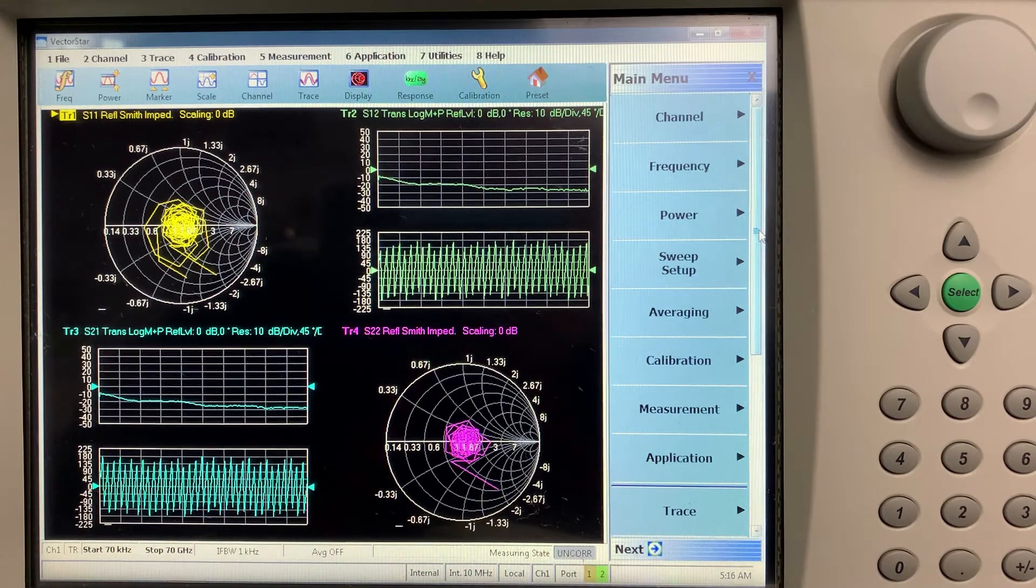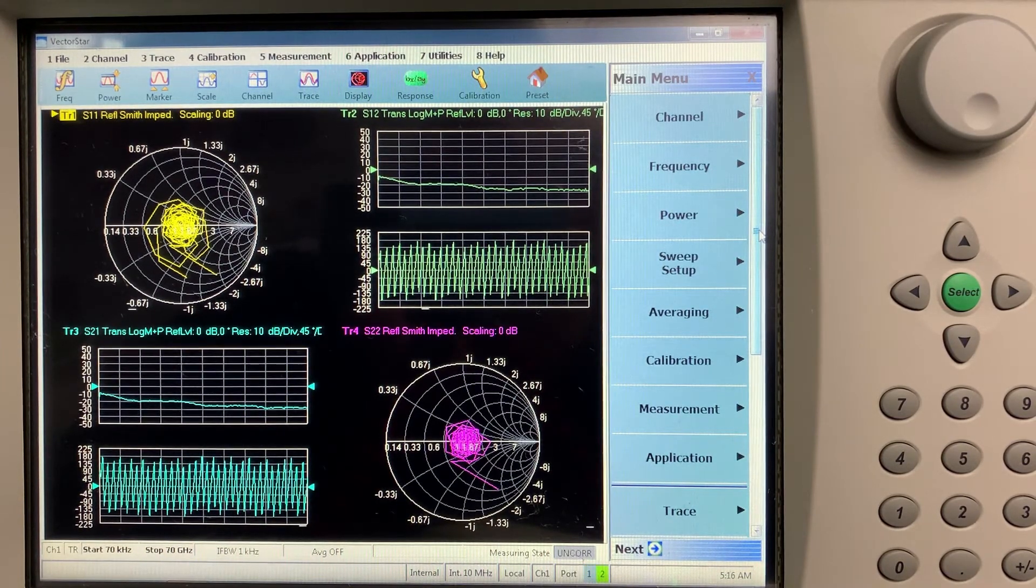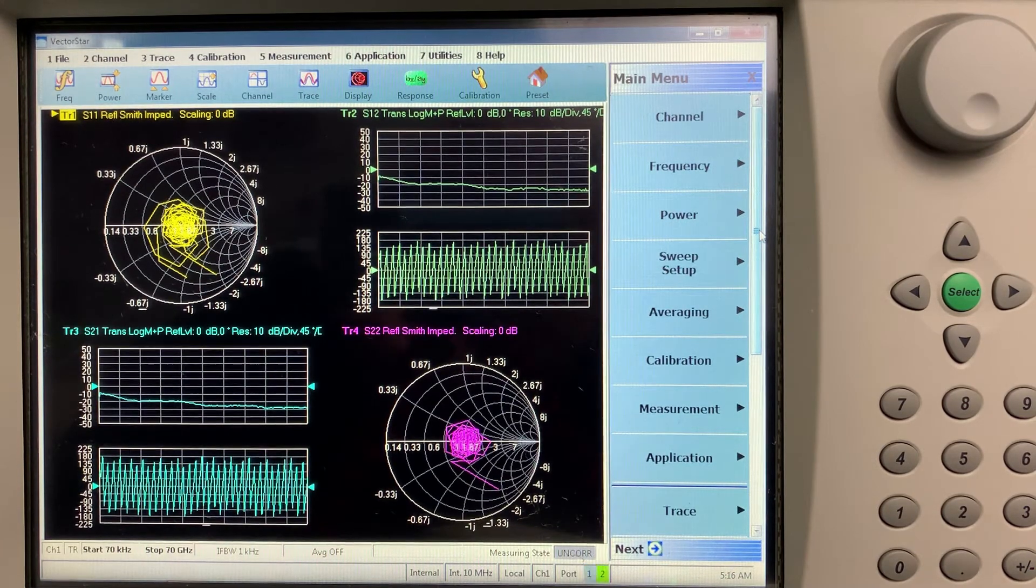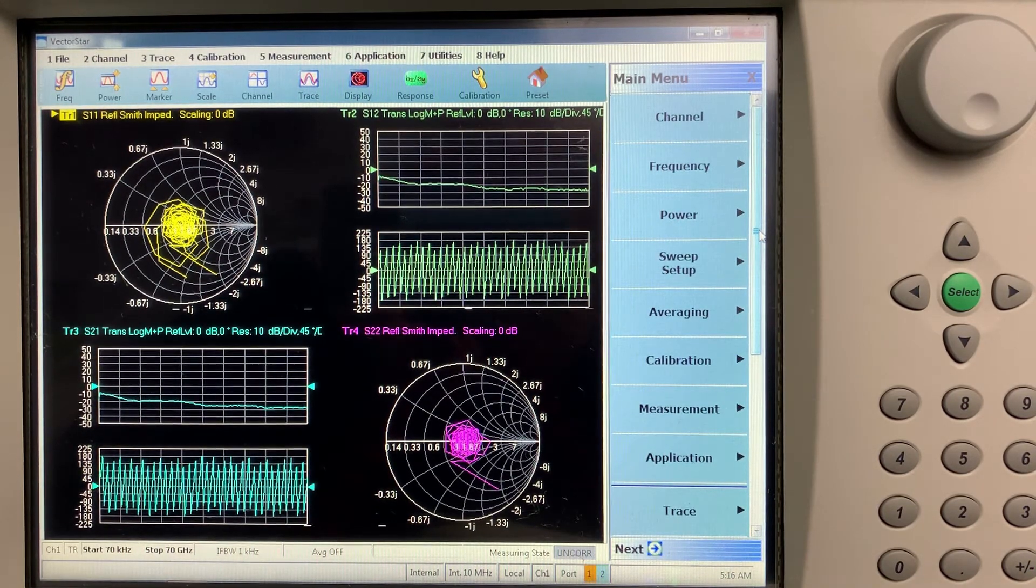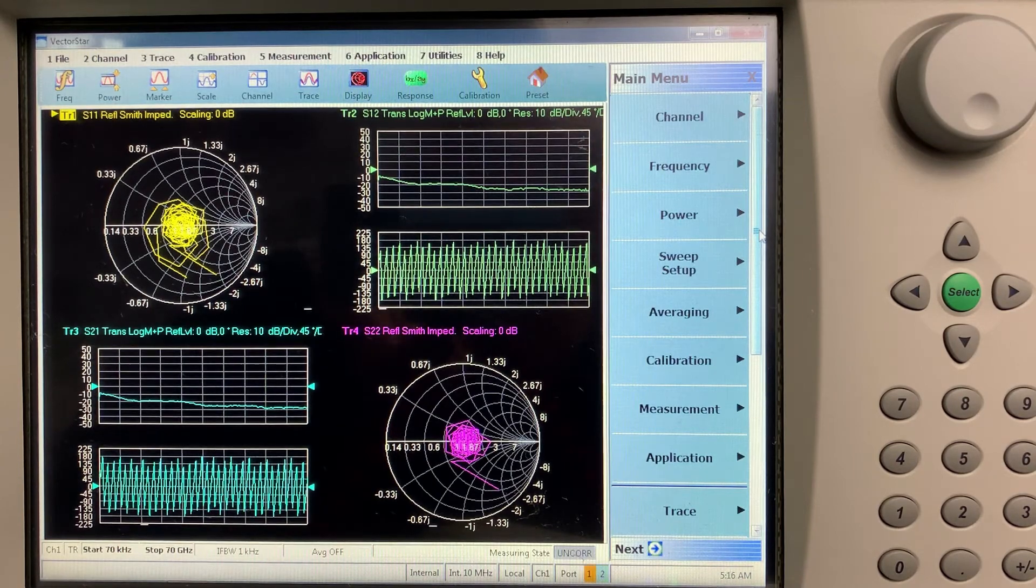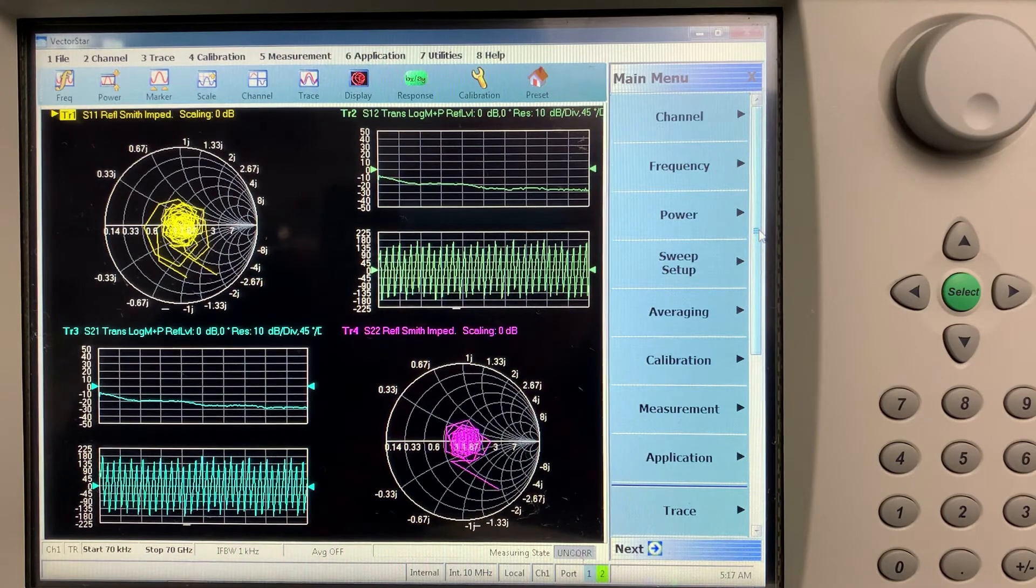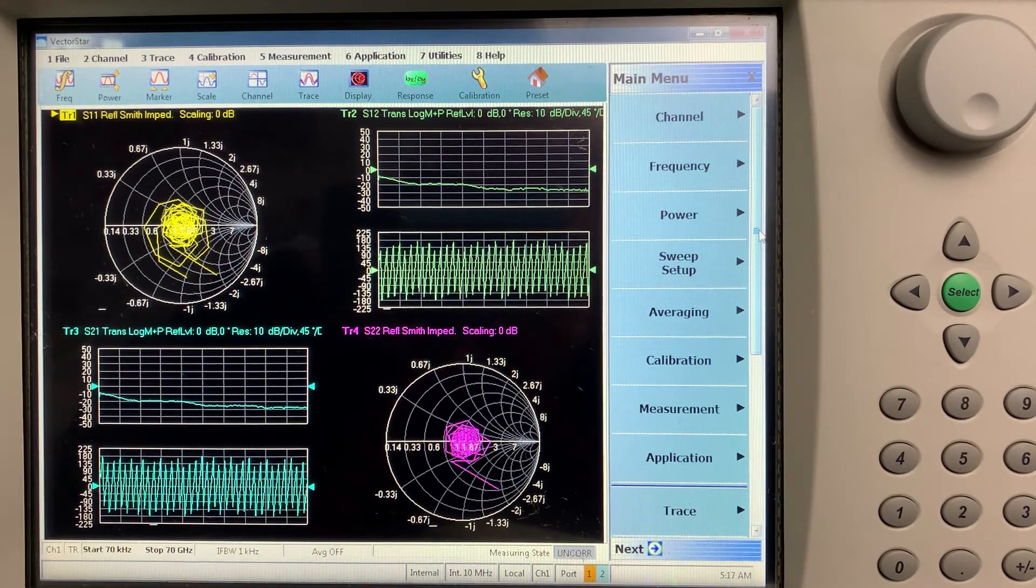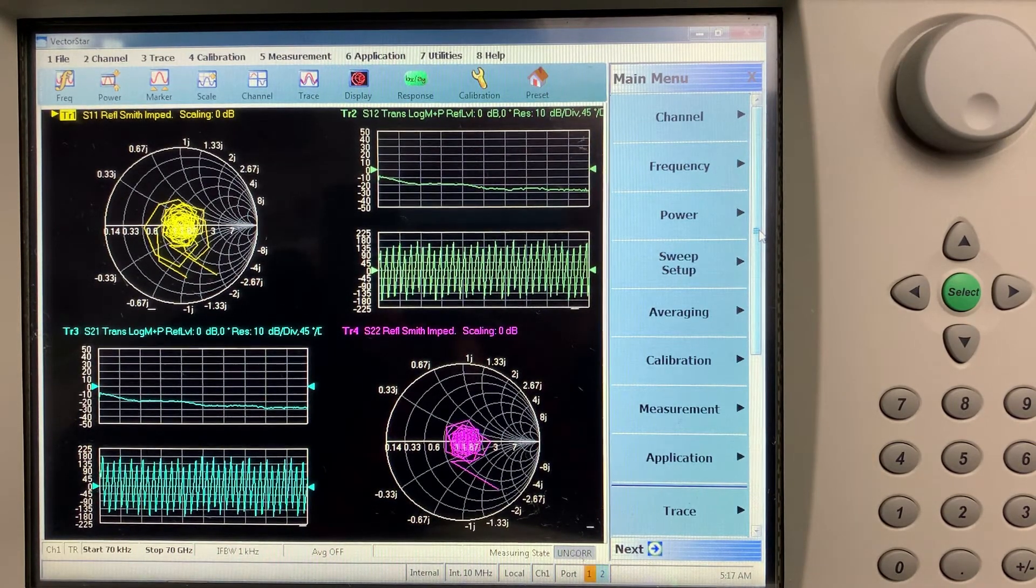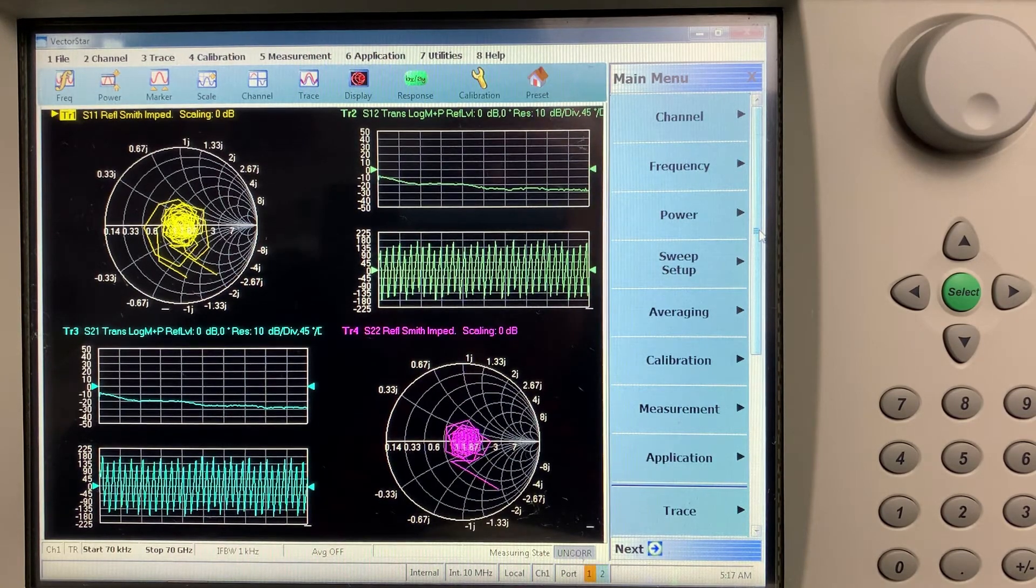However, because the Auto-Cal method is a transfer method based on the LRL calibration, it provides better corrected characteristics than any short open load through manual calibration, even if using a sliding load. Coupled with the fact that automatic cals are much faster and less prone than manual calibrations, Precision Auto-Cal becomes the preferred VNA calibration method for all applications from R&D to manufacturing.